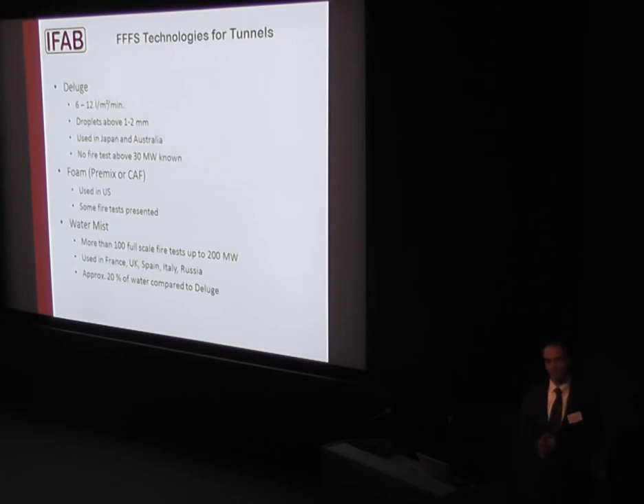From tests that aren't published yet, I can tell you 6 meters is not enough. At 10 to 12 meters, these systems become quite effective. But the problem is, at the moment there are almost no fire tests above 30 megawatts, so they haven't been tested at that scale. Still, they've been used for many years.